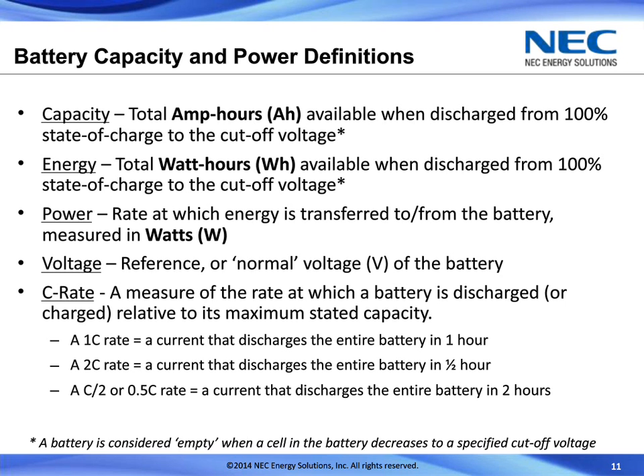Energy of the battery is really the same measure, but it's really the measure of power, watt hours. So it's a combination of the amps times the voltage changes as it's being discharged. And again, from 100% full or 100% state of charge down to zero or an empty charge, which is defined by the cutoff voltage. The power that the battery is capable of delivering is the instantaneous energy flow, or the rate at which energy is transferred from the battery, measured in watts. And then voltage, hopefully, is fairly obvious to us who are interested in batteries.